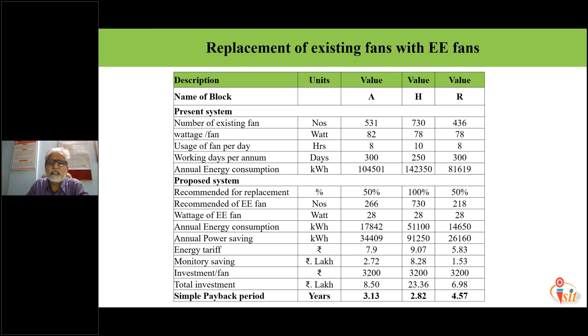Annual energy consumption would be 17,842 for these 266 fans. Annual power saving would be 34,409. Tariff is 7.9, monetary saving is 2.72 lakh. Investment, taken on the higher side, is 3,200 per fan; total investment is 8.50 lakh, and simple payback is 3.13 years. So like that, we give them analysis of all this — we take the reading, recommend an energy efficient fan, and submit the payback analysis for the fan.